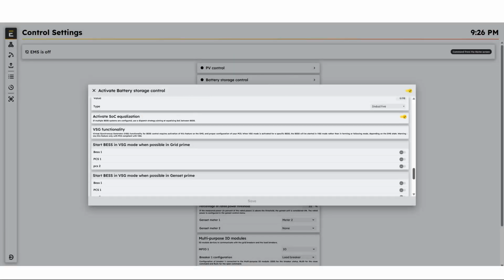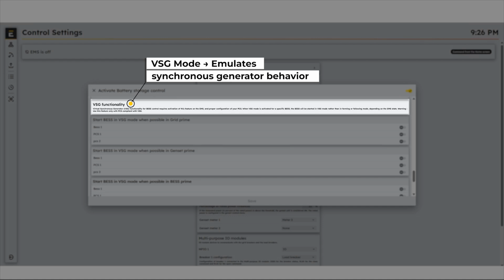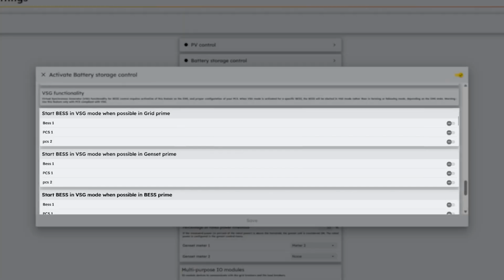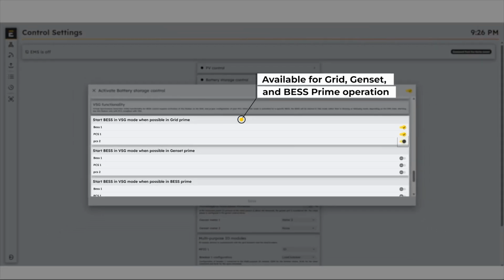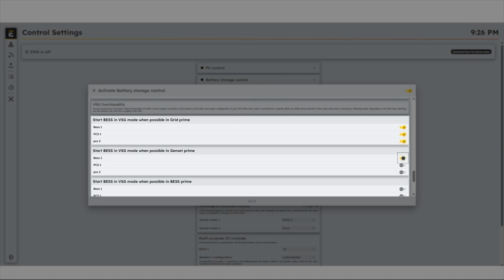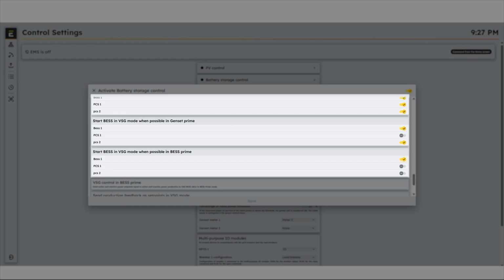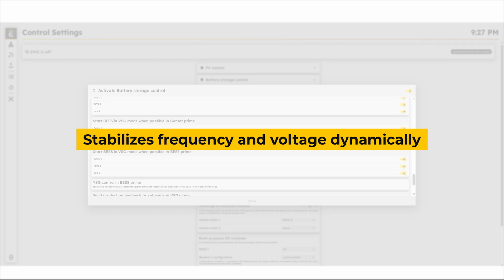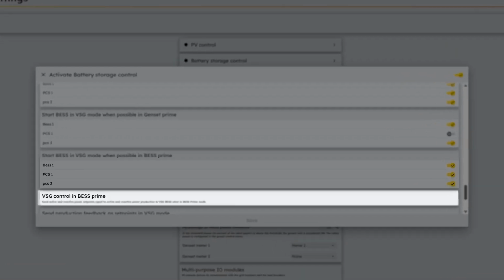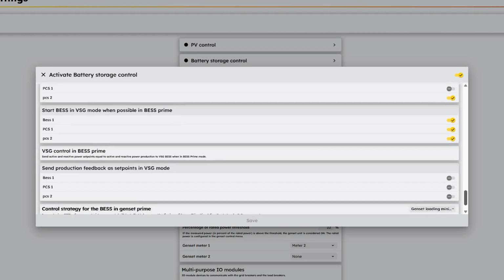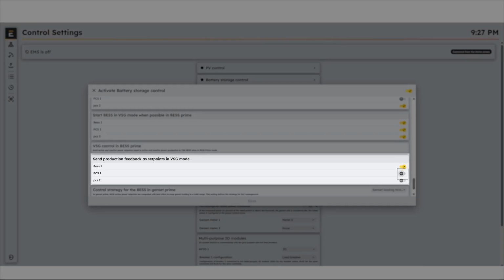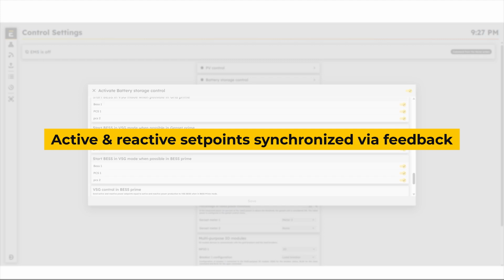The Virtual Synchronous Generator, or VSG functionality, allows the BESS to behave like a traditional generator by emulating inertia and frequency response. It can be enabled in Grid, Genset Prime, or BESS Prime modes, ensuring dynamic stability across hybrid systems. When active, the BESS contributes to grid resilience by regulating frequency and voltage as a synchronous generator would. The VSG control feature ensures both active and reactive set points are aligned, while the production feedback option allows the EMS to send real-time power data for precise synchronization.